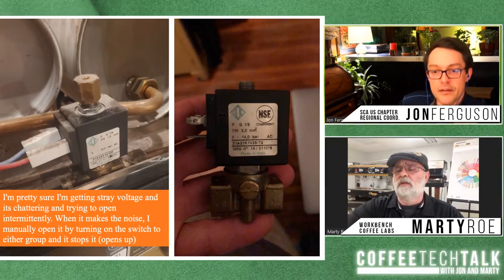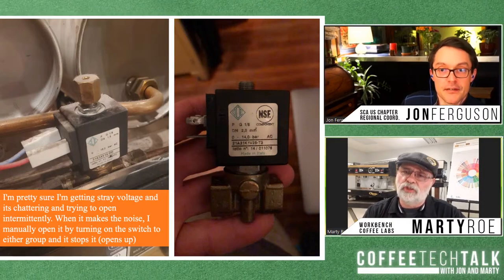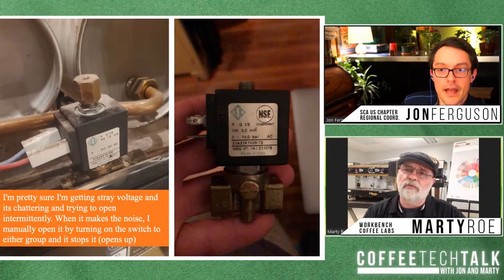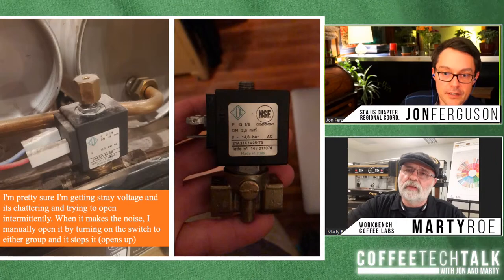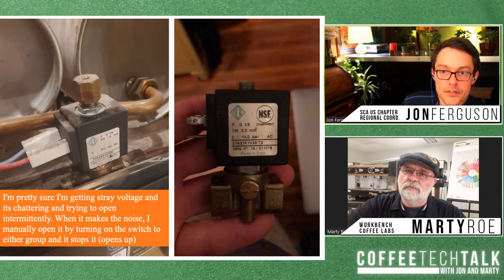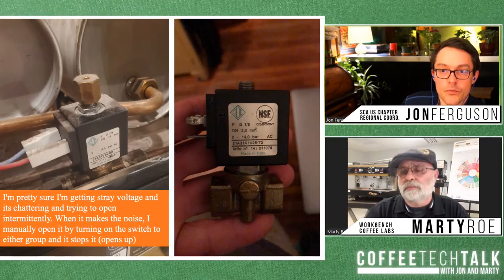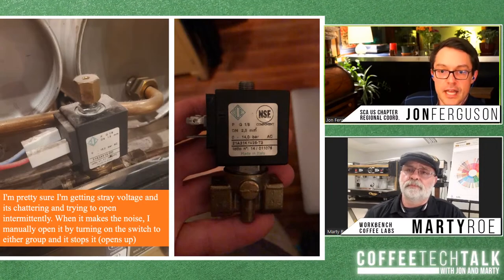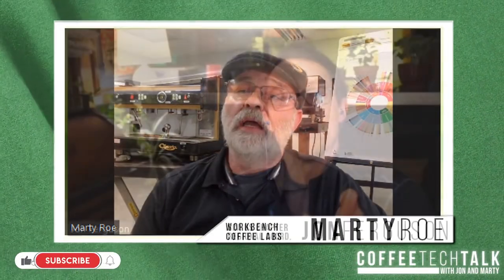And so I would say the first recommendation is to check your building. Check your voltage. Right. And then, if you can't correct that, or even if you can, go get a coil that is rated to that lower, correct voltage. So the one on the right will not work. It's not a bad coil, it just doesn't have the right power. Correct. And that happened in Omaha too. Same machine, a different building, but the exact same instance. So this is great. This happens often.